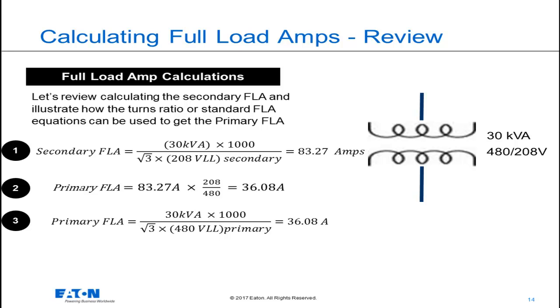We can calculate the secondary full load amps as shown in equation 1. That full load amps is 83.27 amps. So I'm now going to calculate the primary full load amps, and I'm going to do that two ways.